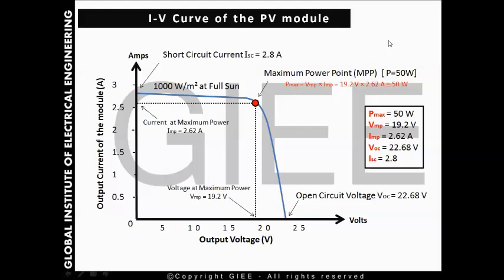So the maximum power is 50 watts at Standard Test Condition: 1000 watts per square meter, air mass 1.5, and temperature 25 degrees Celsius. The voltage at maximum power, V_MP, is 19.2 volts, shown on this point on the curve. The current at maximum power, I_MP, is 2.62 amps. The open circuit voltage of 22.68 volts is greater than V_MP, and the short circuit current of 2.8 amps is greater than I_MP.